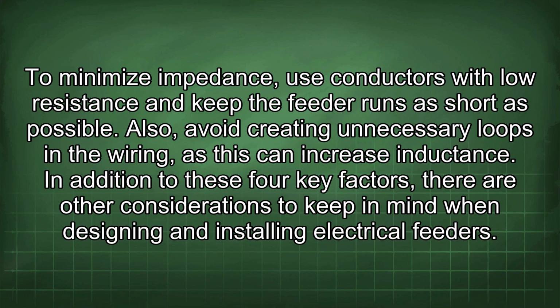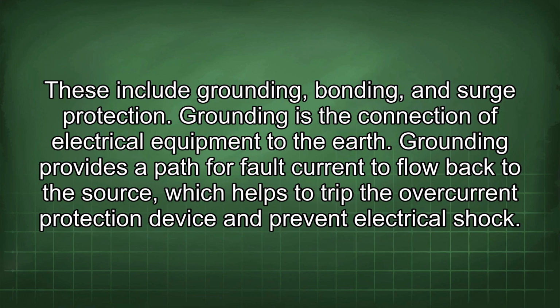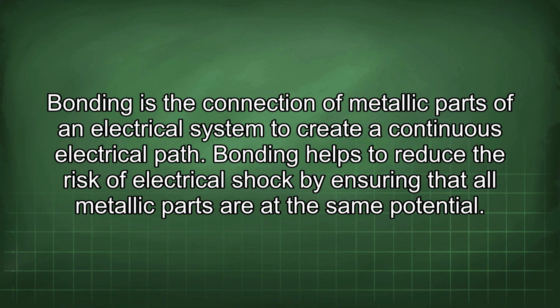In addition to these four key factors, there are other considerations to keep in mind when designing and installing electrical feeders. These include grounding, bonding, and surge protection. Grounding is the connection of electrical equipment to the earth. Grounding provides a path for fault current to flow back to the source, which helps to trip the overcurrent protection device and prevent electrical shock. Bonding is the connection of metallic parts of an electrical system to create a continuous electrical path. Bonding helps to reduce the risk of electrical shock by ensuring that all metallic parts are at the same potential.